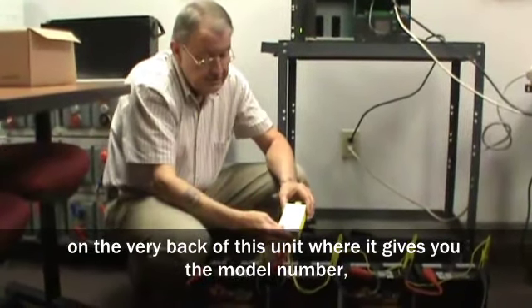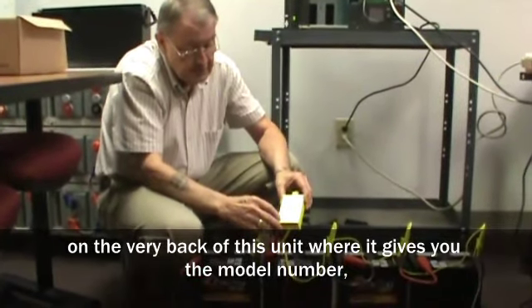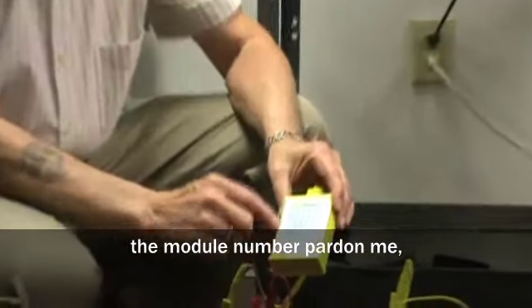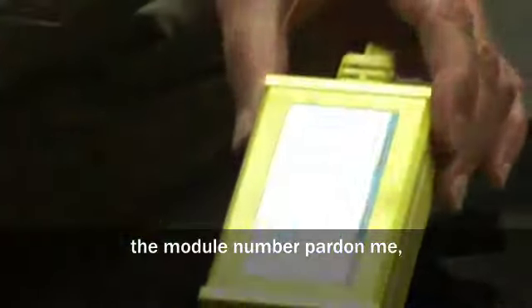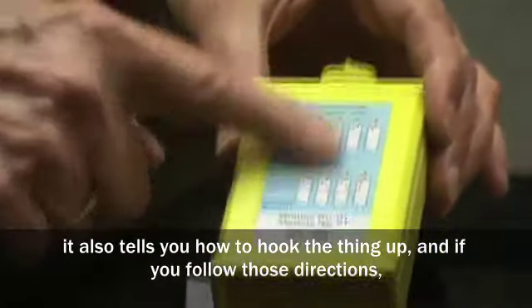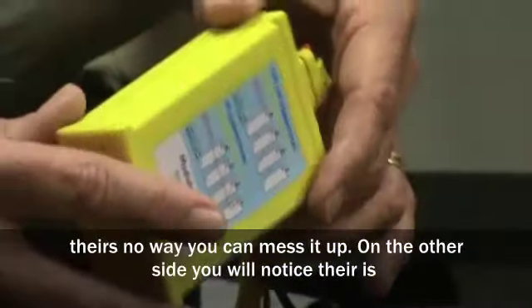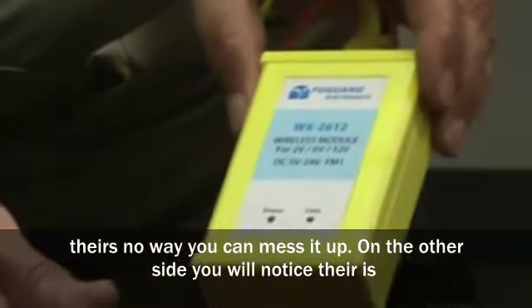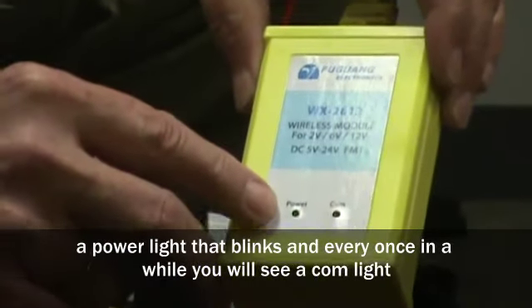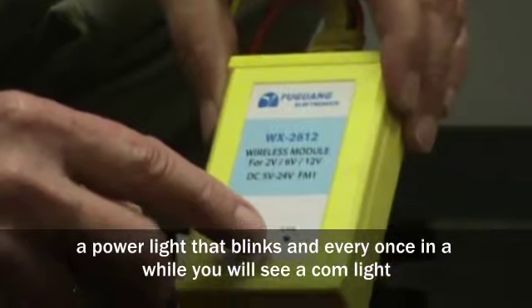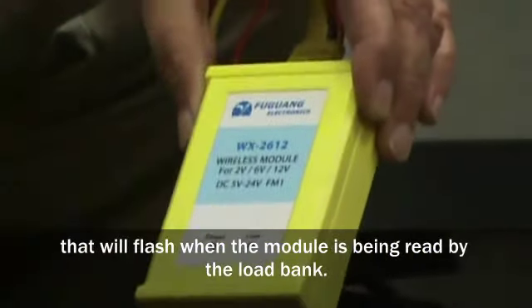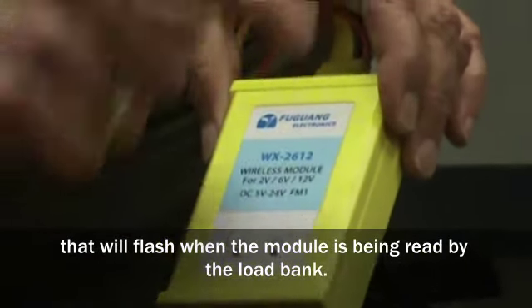On the very back of this unit, where it gives you the model number, the module number, pardon me, it also tells you exactly how to hook the thing up. And if you follow those directions, there's no way you can mess it up. On the other side, you'll notice there's a power light that blinks, and then every once in a while you're going to see a comm light that will flash when the module is being read by the load bank.